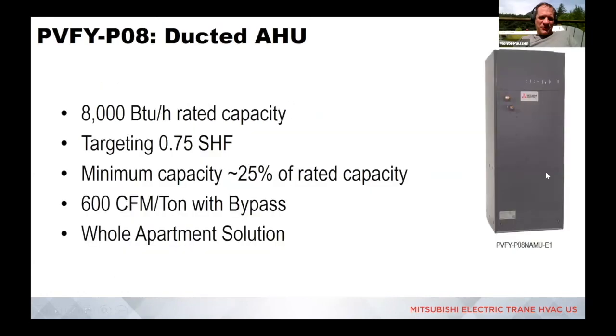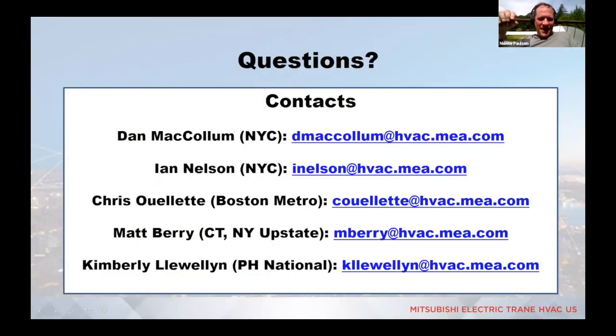You covered most of it, but as you've discussed, I have a new question. I assume you'd want to put that jump box, where you're converting from the VRF system to the hydronic system, in a public space rather than in an individual unit, so that there's no risk of the higher level of refrigerant draining into a bedroom or something. Is that a correct assumption? That is a very correct assumption. Yes, you would want to put that BC controller in a spot where, the larger the space, if you have a mechanical room, I think that'd probably be a beautiful spot to put it. Somewhere where the total refrigerant for the system isn't going to cause you any ASHRAE 15 headaches.